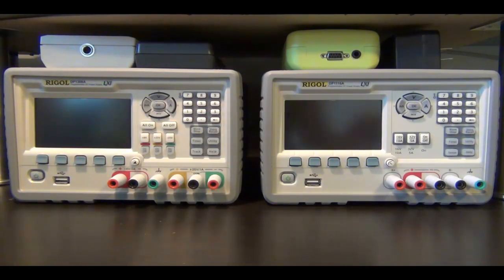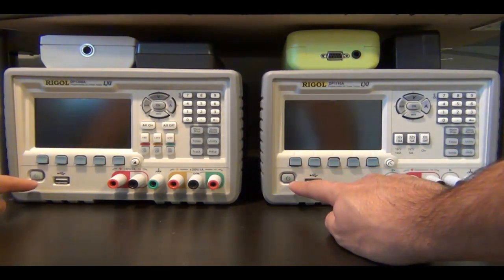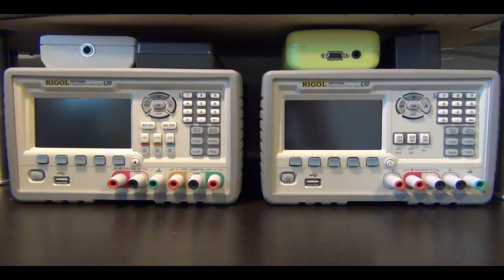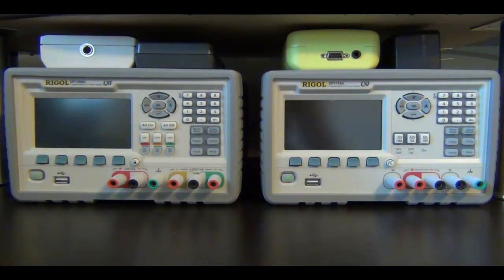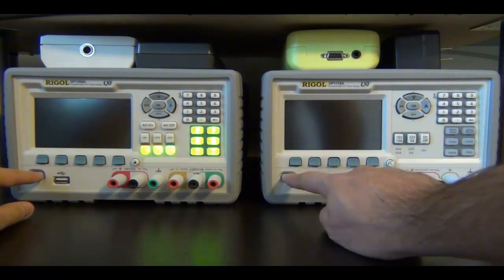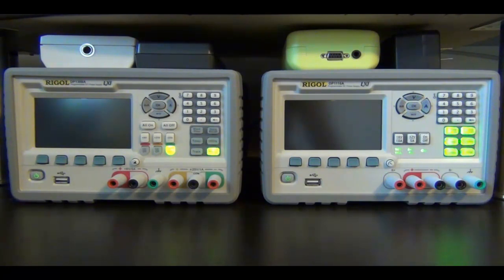So now I've also turned on the hard power switch at the back, so the power supplies are in standby mode. You can tell that the soft switch in the front glows on and off slowly. So if I turn this overhead light off, you may be able to better see it. You can see that they turn on and off, letting you know that they're in standby mode. So I'm going to turn them on at the same time. There we go. They go through a quick self-test and they power on.